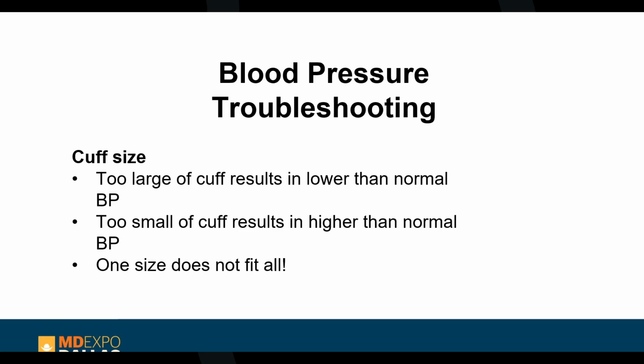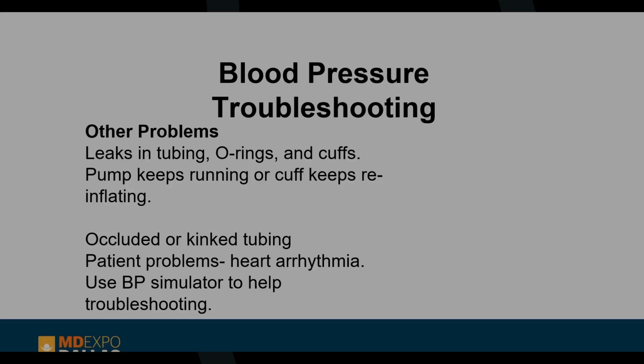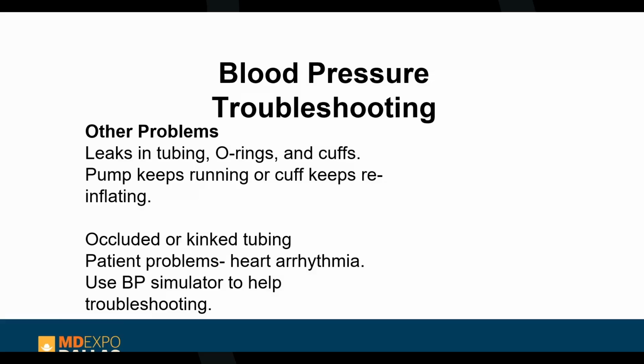Too large of a cuff can result in lower than normal blood pressures, and too small of a cuff, which is what I see more commonly, can result in too high of a blood pressure. Not one size fits all. So if you go to a clinic and they say their blood pressures are reading too high or too low, ask what cuffs they are using. If they pull out one cuff and say, we use this cuff on everybody, that's the wrong answer. You need different size cuffs for different size patients. I have a picture in just a minute, we'll look at that.